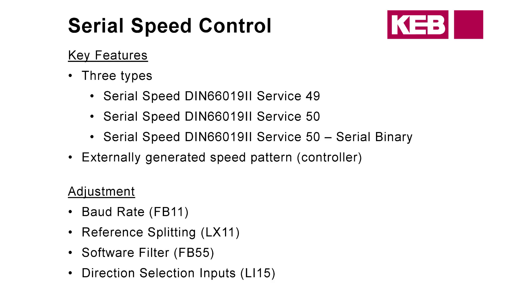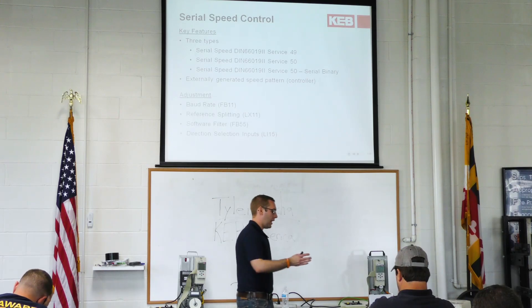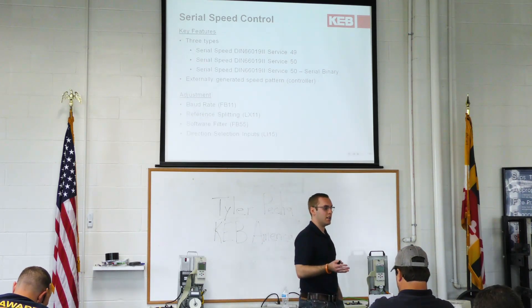Compare that to GAL, for example — they control the whole pattern. So if you're looking to make adjustments on jerk rates, accel rates, that type of thing, you would make them in the controller. But with SmartRise, since we are actually generating the accel and deceleration ramps, you would make them internal to the drive. Some adjustments include the baud rate — that's the communication rate between the drive and the controller — reference splitting, software filter for ride quality, and direction selection inputs.